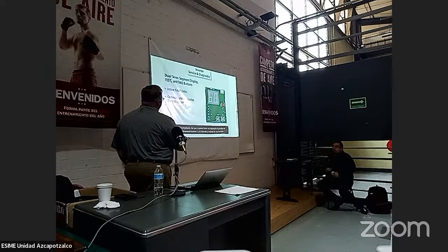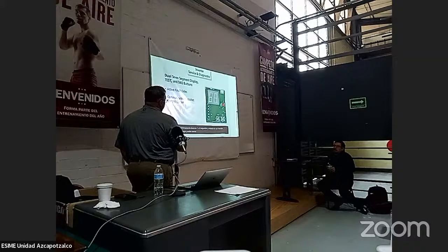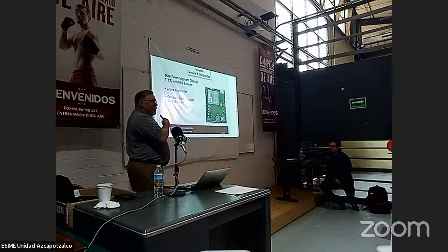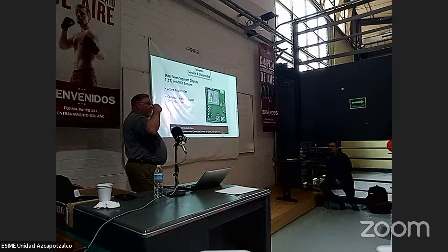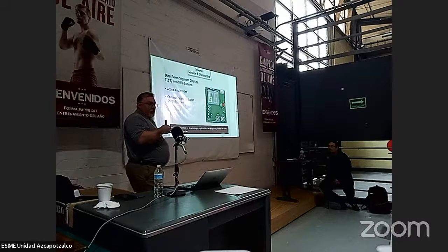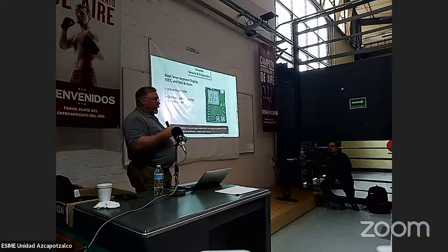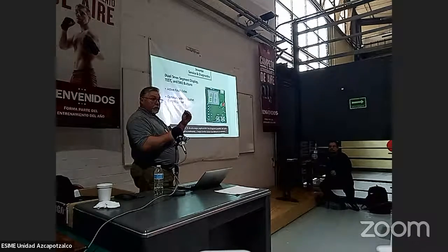Right, and then you can go into active faults once you get there, and it'll tell you what your active faults are. That is also communicated to the control center. So that fault that's on the outdoor unit, it gives you a better explanation. If you go to the Ethernet, you can see what the fault is, and it'll tell you what it actually is. And then you can look that fault up in the manual. It'll tell you how to troubleshoot that fault.